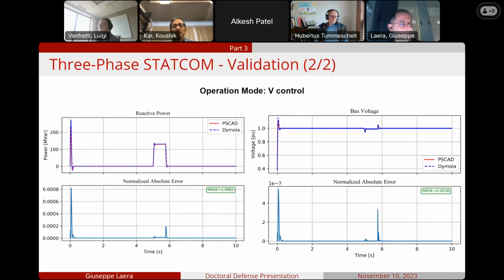The second scenario that has been considered for the validation is the operation mode in voltage control. In this case, we can see the presence of a three-phase fault to ground applied at 5 seconds. So we have an initial oscillation of the reactive power injected by the STATCOM that is necessary to make the bus voltage reach 1 per unit. And then it stays at that value, and the reactive power is maintained at 0. Once the fault is applied at 5 seconds, the STATCOM reacts by injecting reactive power.